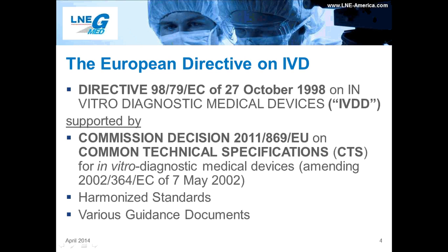The topic of this discussion is concerning the technical files and design dossier requirements within the scope of the current IVDD. This does not include the proposed regulatory changes to the directive. We have a separate webinar planned to discuss those proposed changes, and it's being presented by Sarah Steck, who is the Legal and Regulatory Manager at GMED North America. For the purposes of this presentation, we will focus on the current European Directive on IVD 98/79/EC. The IVDD is supported by the Common Technical Specifications for In Vitro Diagnostics Medical Devices, harmonized standards, and various guidance documents such as the MEDDEV.